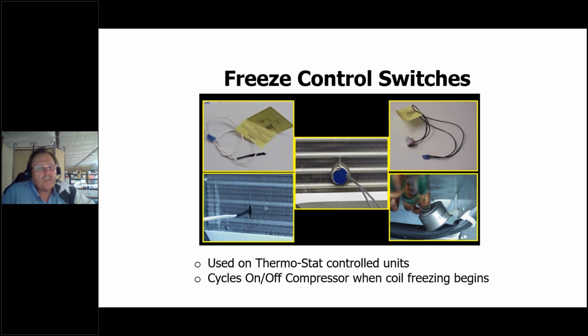But that freeze control switch, if it falls out of those fins or it comes loose, like see that little disc in the bottom right-hand picture, if that little clip-on disc comes loose off of that coil, then it's dangling down below. And so even though the air conditioner now begins to start freezing up, because the sensor is not measuring the temperature of those coils, it's going to allow it to freeze up. And so we're over here trying to figure out, okay, I know this thing's got a freeze control, but if the freeze control falls out of position, then it tells that air conditioner, hey, you just keep going, everything's going fine. When it may not be.